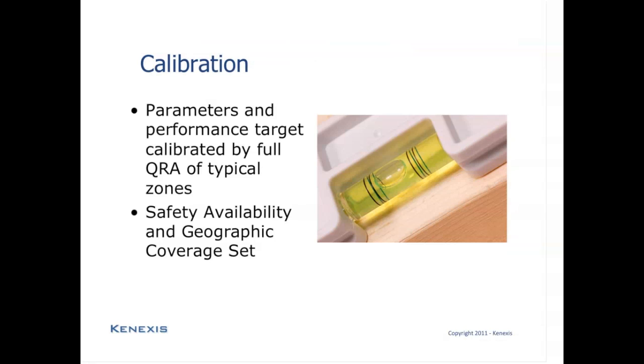The primary factor that is going to determine whether or not a semi-quantitative approach is going to ensure that tolerable risk levels are achieved is a detailed and comprehensive calibration of the tables and the performance targets that are used in the semi-quantitative approach, to ensure that when a grade C is selected, the associated safety availability and coverage targets will allow tolerable risk to be achieved. This calibration process is typically going to be performed by doing a full QRA of some typical process zones that have been given typical performance targets or zone grades.